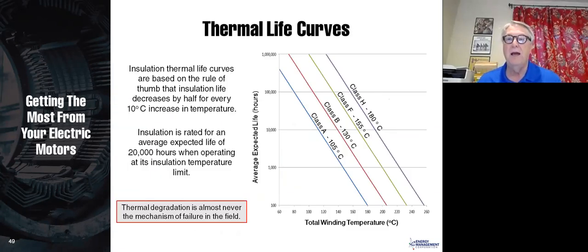Now here's your thermal life curves. And I think this is kind of academic. They say that for every 10 degrees increase in temperature, you will decrease your insulation life in half. But normally we're not running at these temperatures. And in fact, thermal degradation of motors is almost never the mechanism of failure of a motor. So it can be, absolutely can be, but typically it is not. And so this is interesting, but I don't spend a lot of time looking at those thermal life curves.